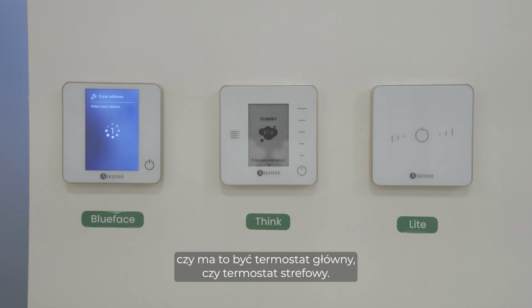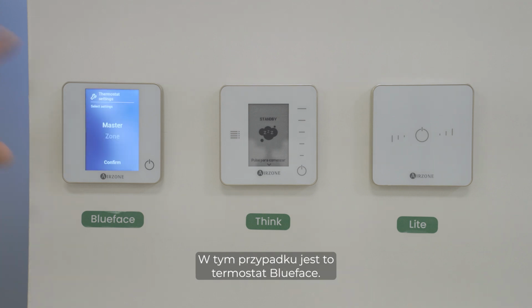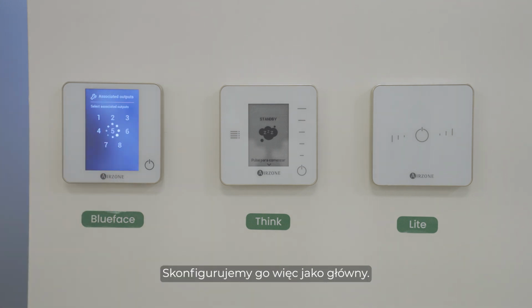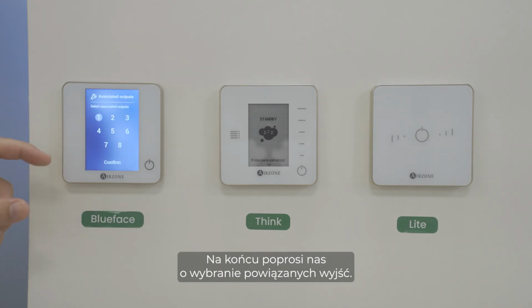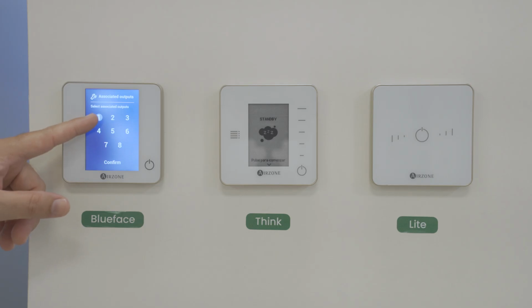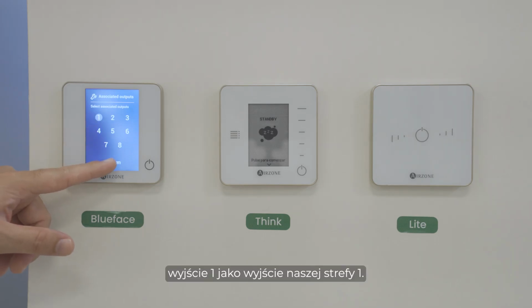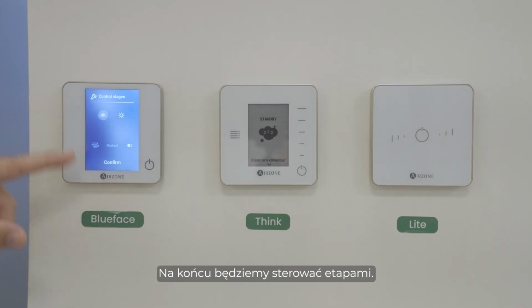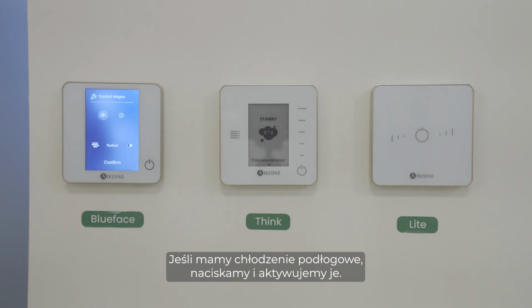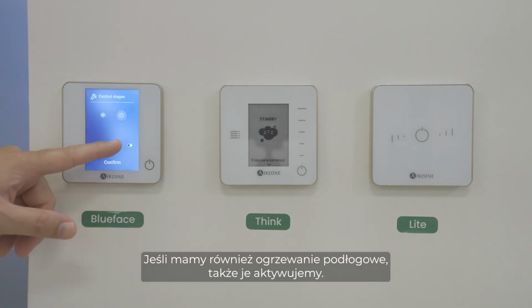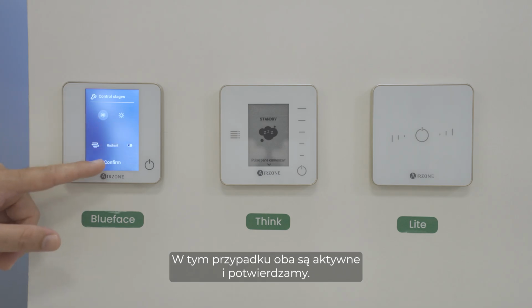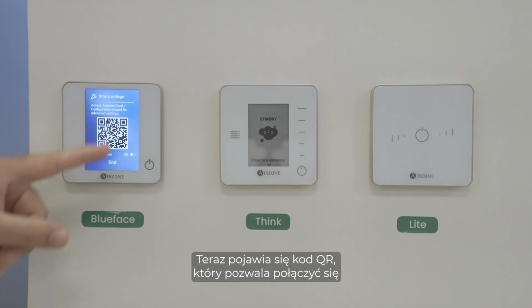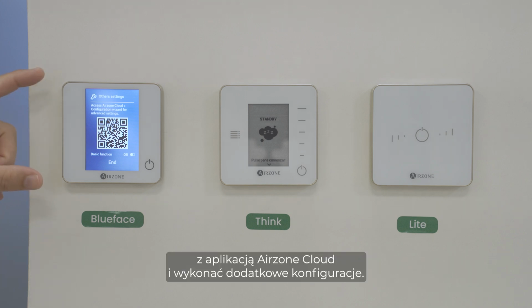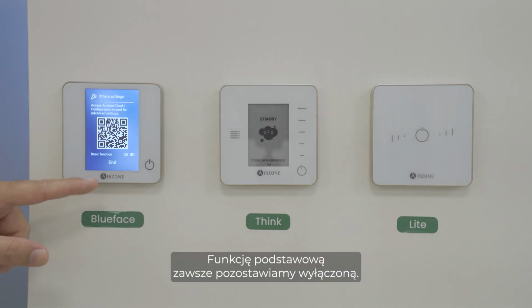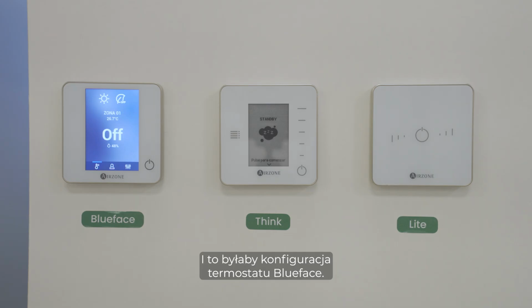Then we're going to confirm if this is going to be a master thermostat or a zone thermostat. In this case, it's the Blueface thermostat, so we're going to configure it as master. And finally, it's going to ask us to select the associated outputs. In this case, we're going to maintain output 1 as our zone 1 output. Finally, we're going to control the stages. So if we've got underfloor cooling, we're going to activate it. And if we've got underfloor heating as well, we're going to activate it. Okay, in this case, we've got both activated and we confirm. Now we get a QR code to be able to link to our Airzone Cloud app and to do additional configurations. And we always maintain the basic function as off. And that would be the Blueface thermostat configuration.